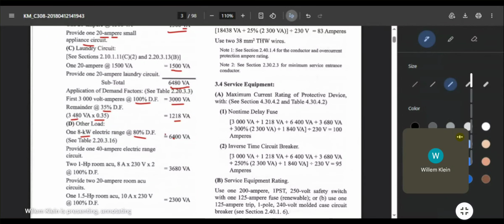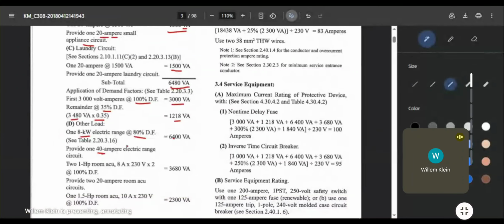So if you're using an 8 kilowatt electric range, you have 80% demand factor for this one, and then you will use a 40 ampere electric range circuit. And then your aircon units, your motors. Remember, this is a heater, but this is not a motor, so you will not use this as your highest rated motor, although this is a very large load, 6,400 VA. So for your aircon units, you have two 1 HP aircon units, both rated at 8 amperes, 230 volts. Times 2, you'll have 3,680 VA, computed at 100% demand factor. That's also mentioned in the sections for the motors.